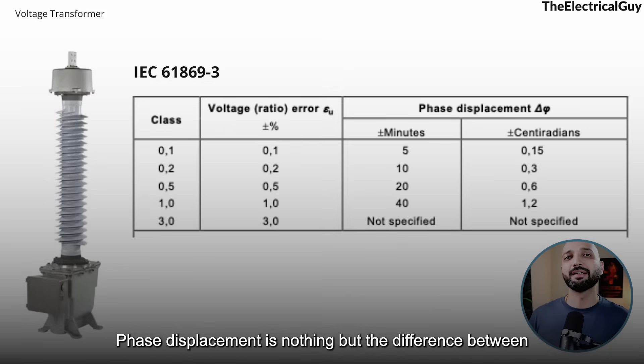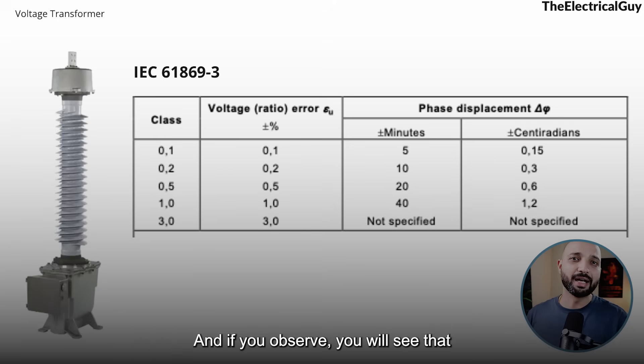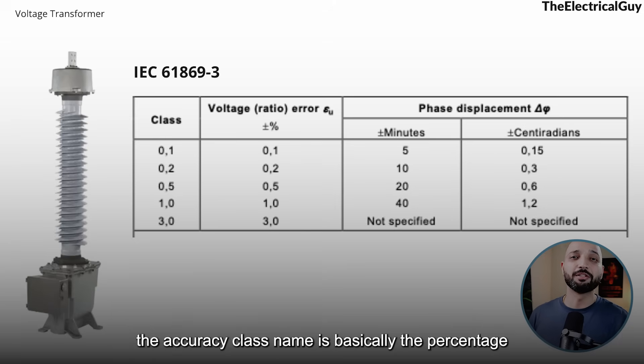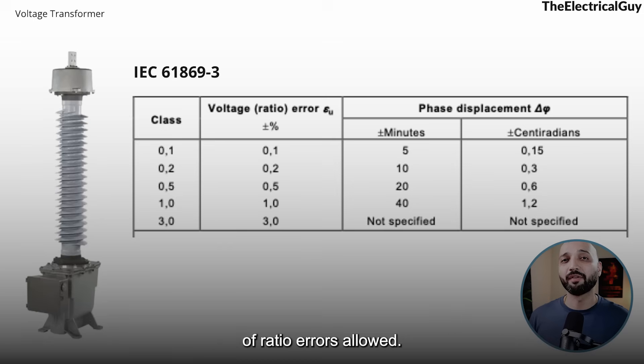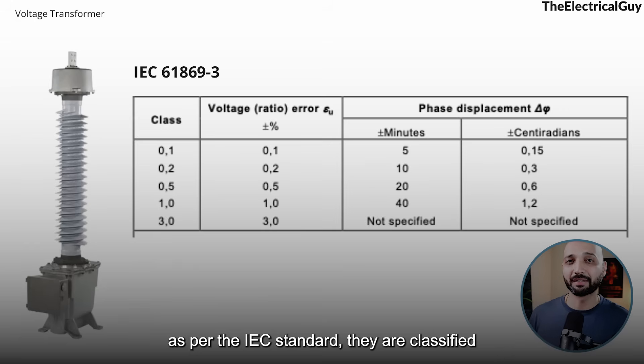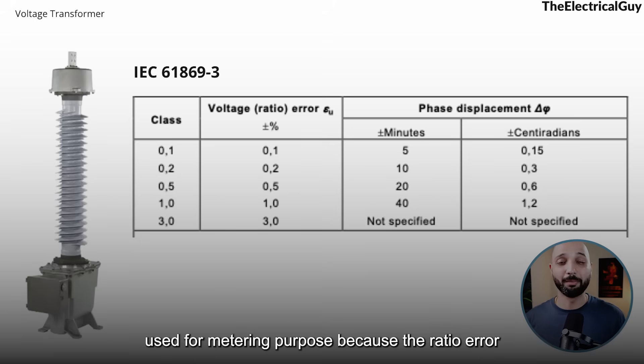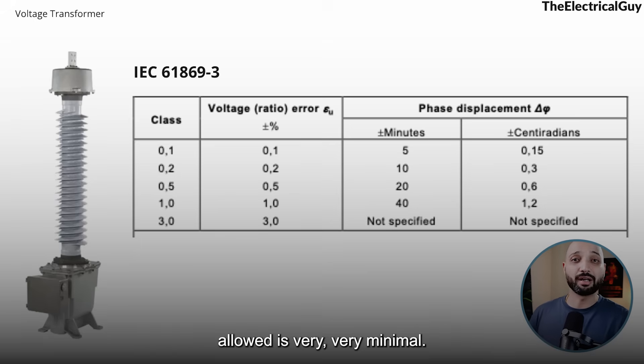Phase displacement is nothing but the difference between the primary and secondary current and voltage vectors. If you observe the table, you'll see that the accuracy class name is basically the percentage of ratio error allowed. So when a core has a ratio error of 0.2%, it is classified as a 0.2 class core, which is used for metering purposes because the ratio error allowed is very minimal.